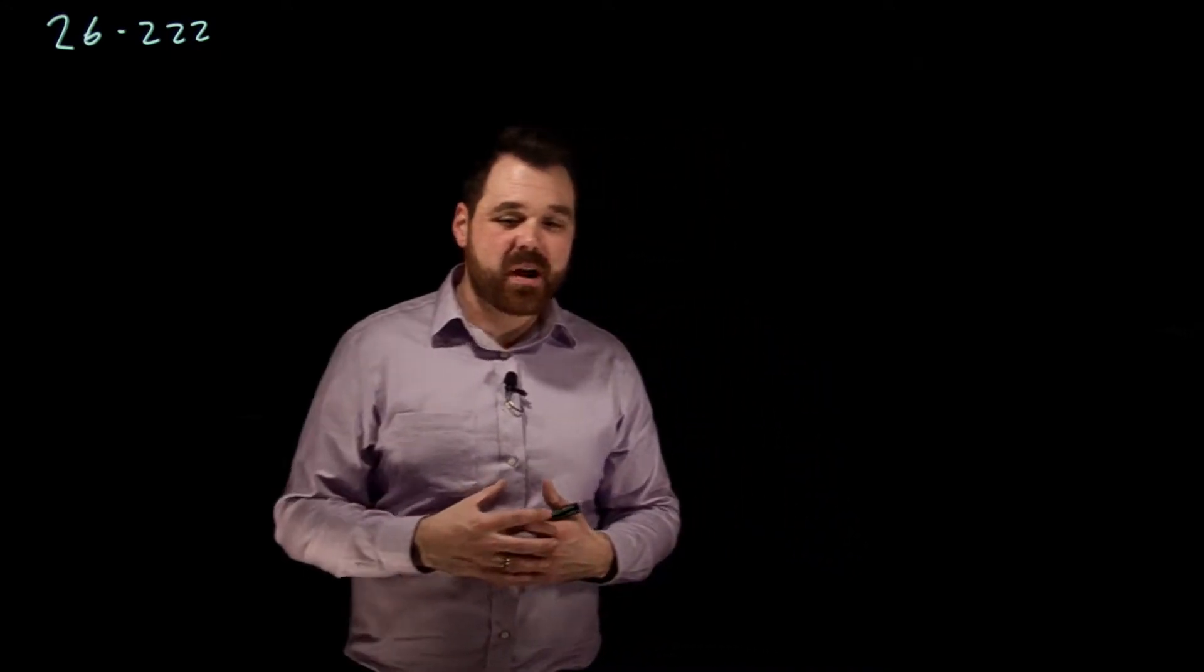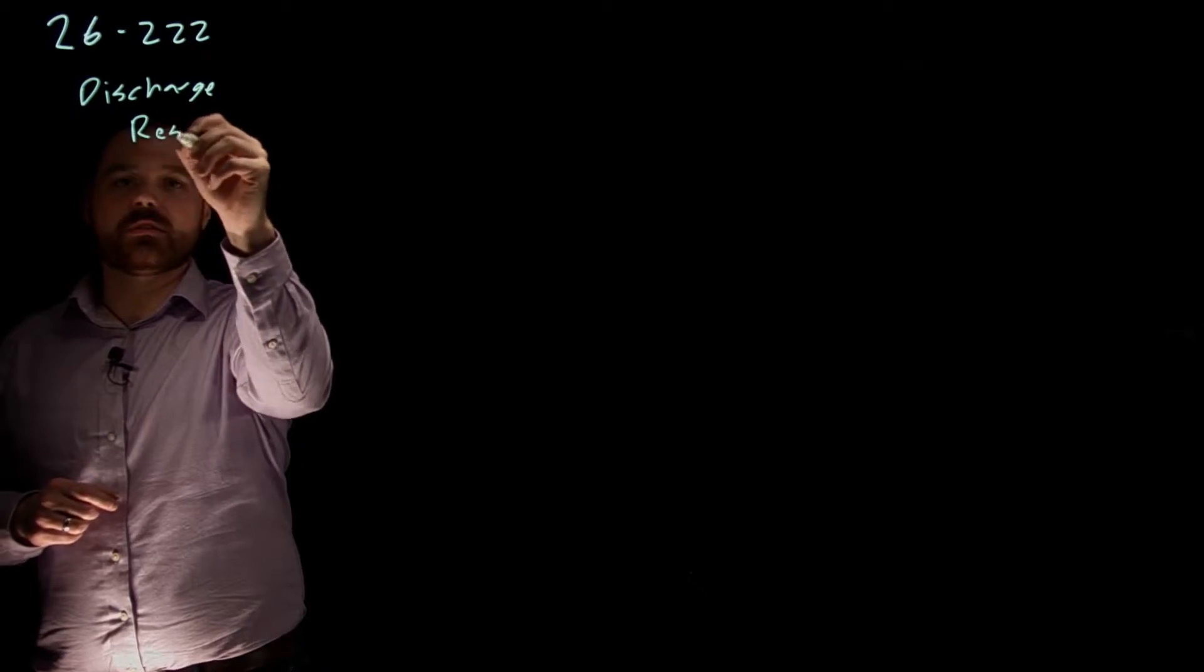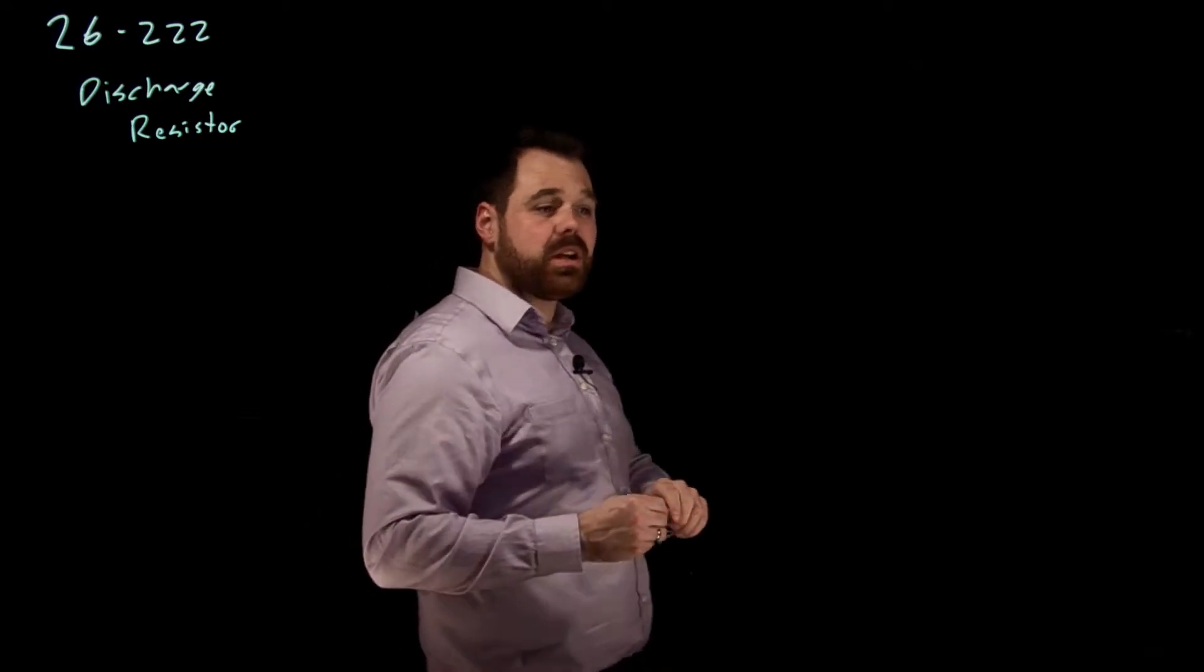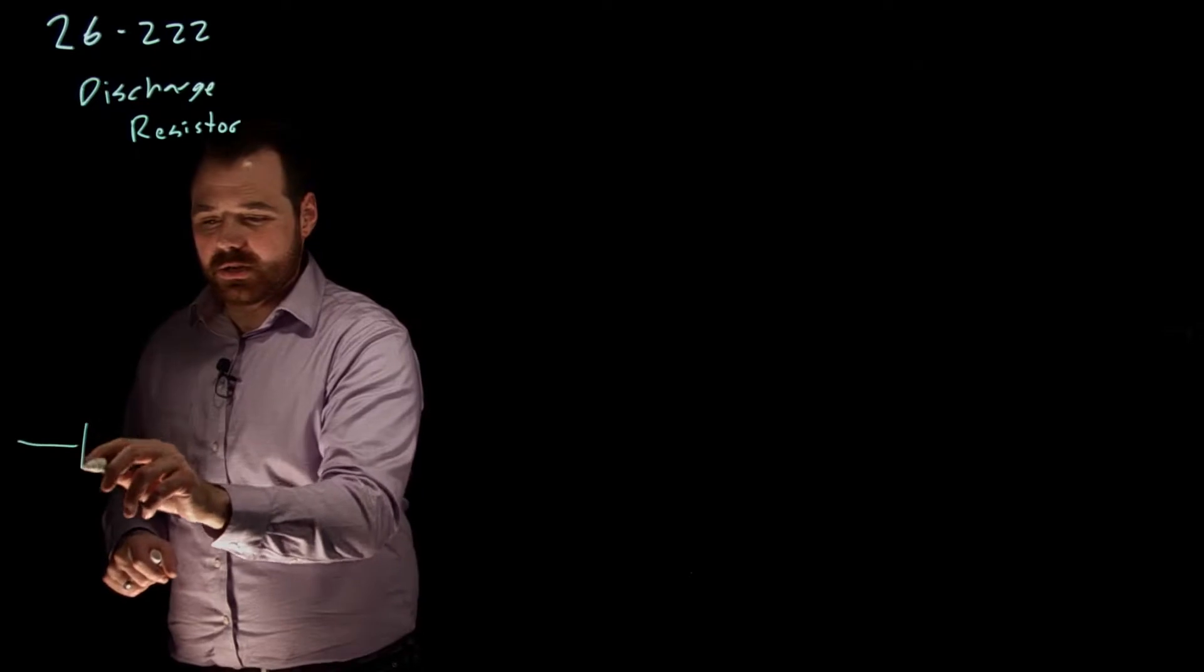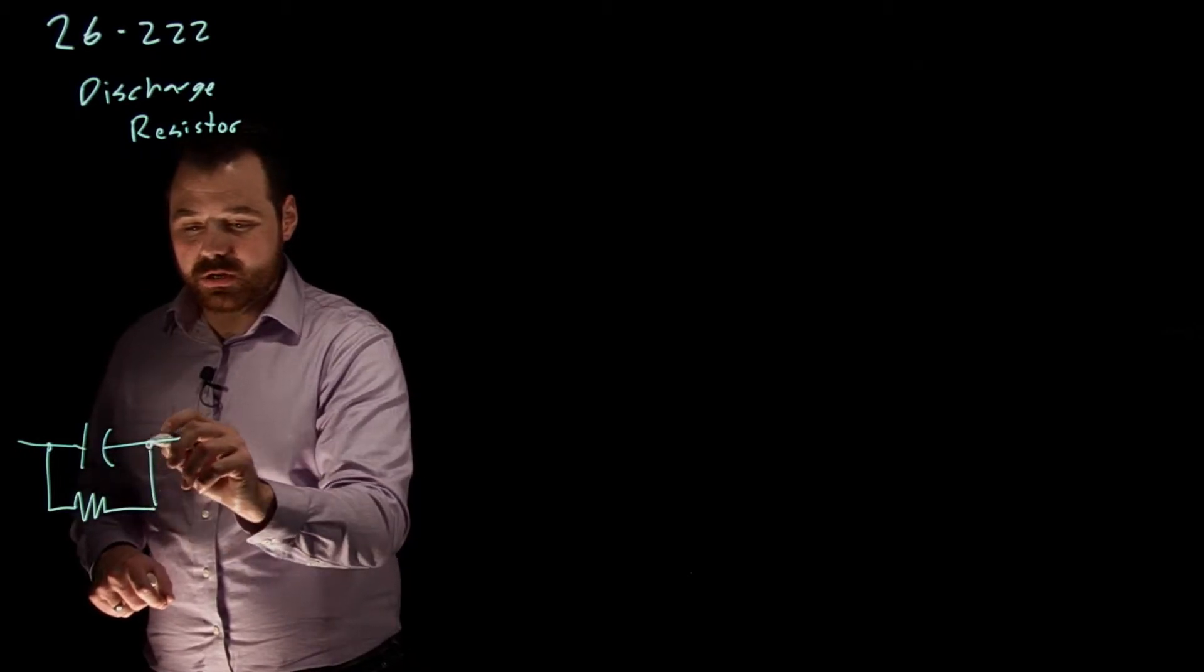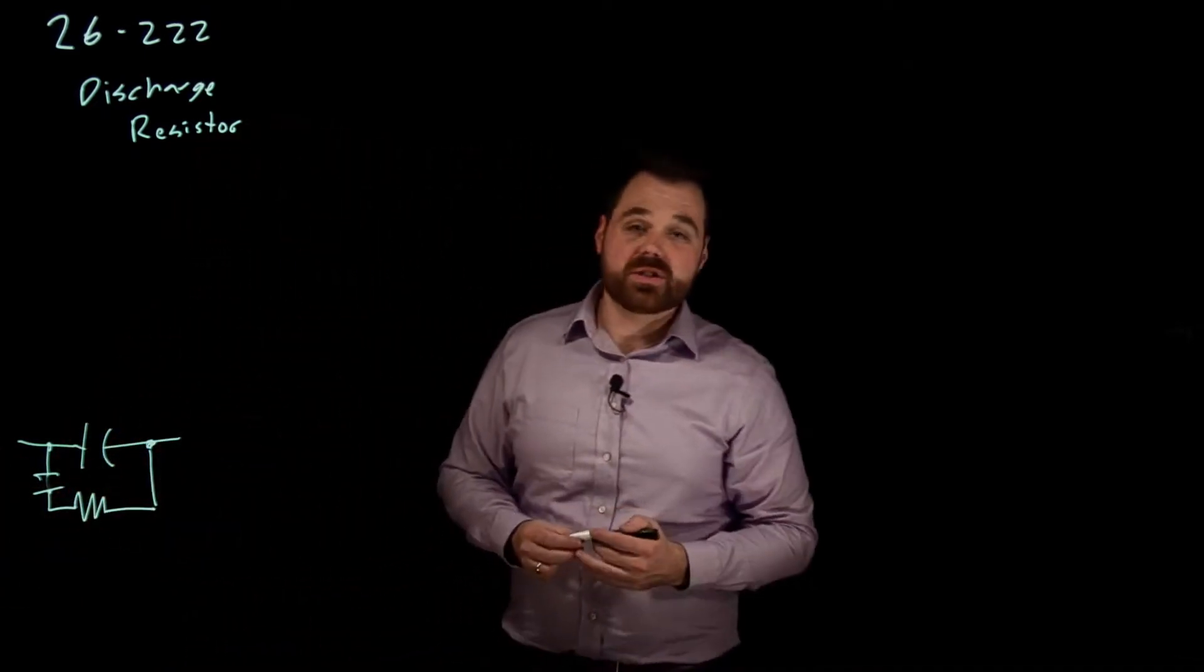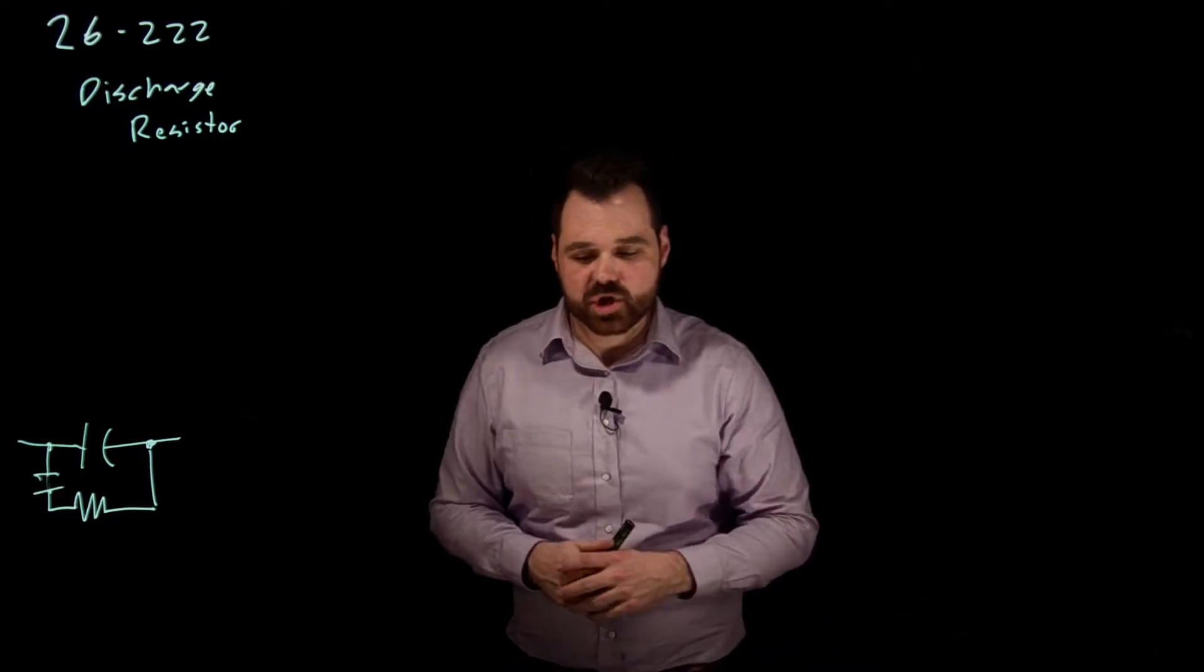What I want to spend a little bit of time on right now is actually sizing what we would call a discharge resistor. So sizing this discharge resistor - this is our capacitor. We would put it in parallel with the cap. And we might have it switched or something by putting in a set of contacts or something like that, some way to put that discharge resistor into the circuit so the capacitor can discharge.